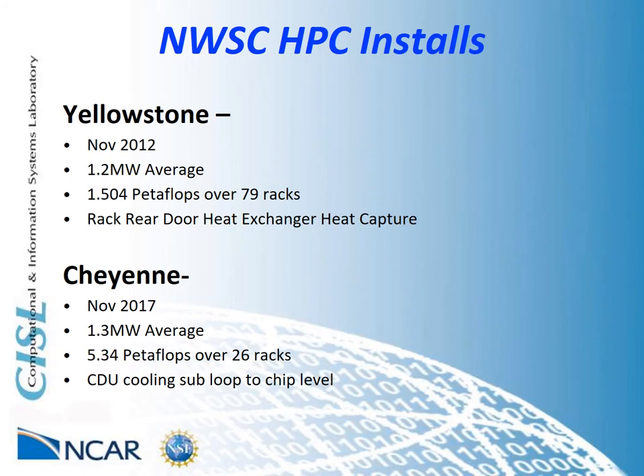Yellowstone was installed in 2012 as the initial high-performance compute system at the NWSC and had an average power draw of 1.2 megawatts with a peak performance of 1.504 petaflops. The total footprint for this system was 79 racks. This HPC system was cooled with rear door heat exchangers, capturing the heat through a large coil mounted to the back of the rack. Cheyenne was installed in 2017 as a second-generation supercomputer.